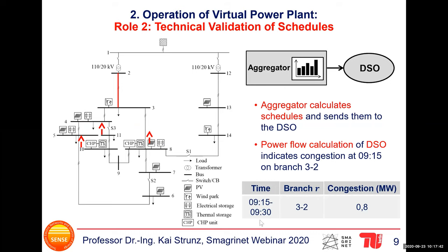And then the DSO notices, oh, at 9:15 in the morning, we have a congestion on the branch 3-2. You see it here, it's shown in red. From 3-2-2 upstream, we have a congestion, and the congestion is 0.8 megawatts too much. So something needs to be done about it. And that's not a rare type of congestion. If we have a lot of renewable energy available, for example, if there is good wind and solar potential, then what can happen is that we have congestion because a lot of power is trying to flow upstream to the other parts of the grid.